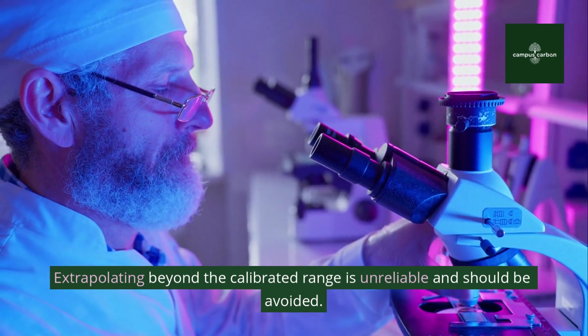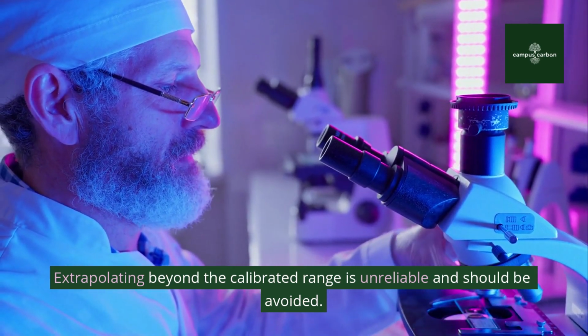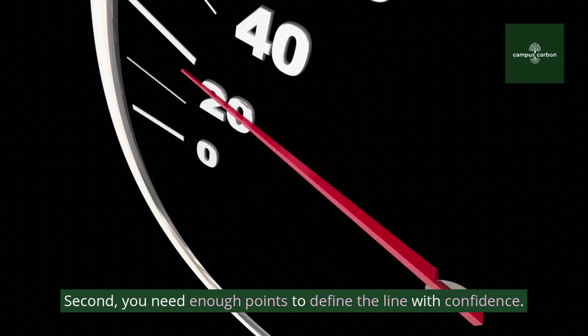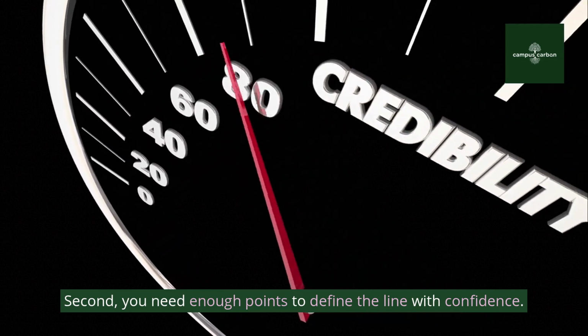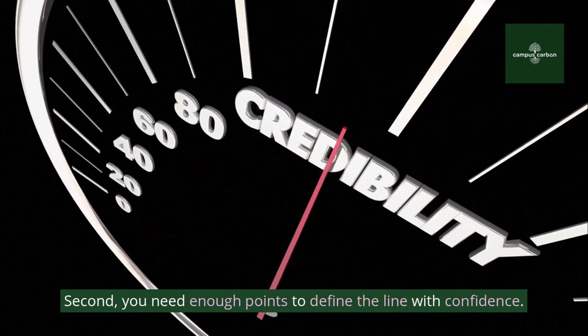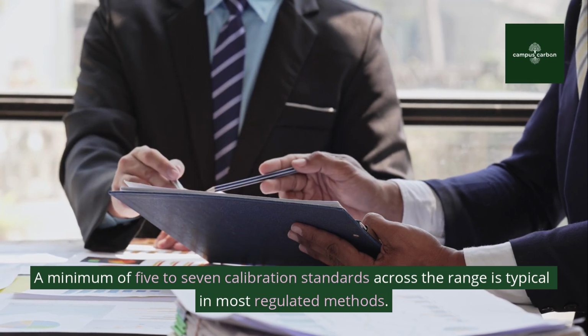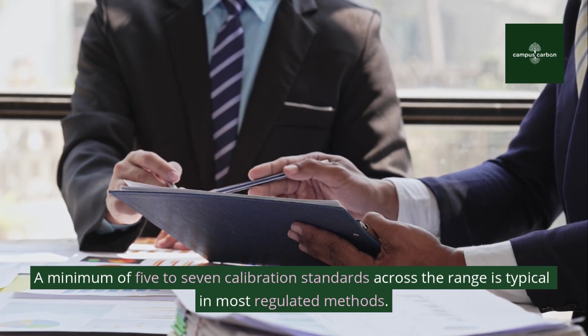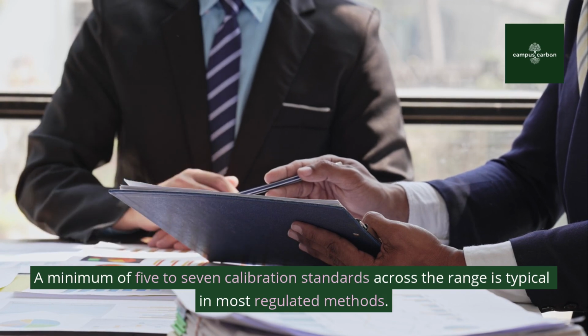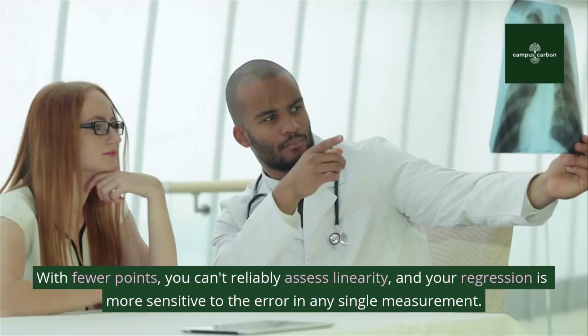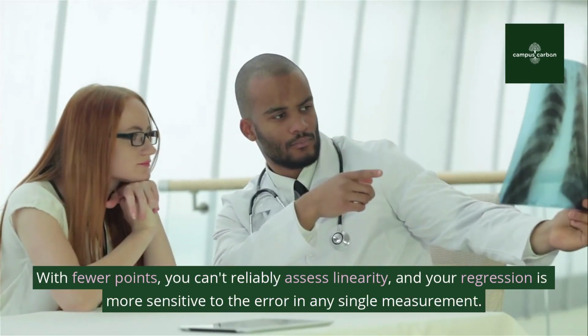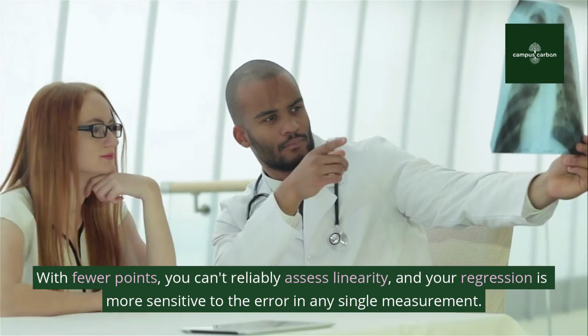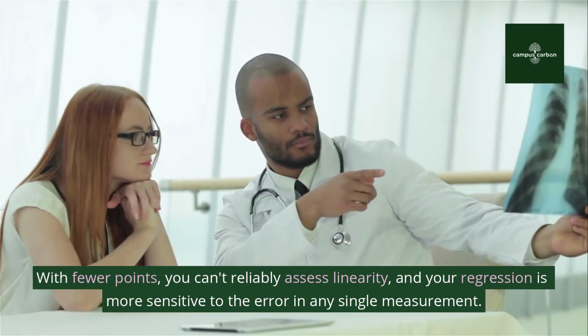Extrapolating beyond the calibrated range is unreliable and should be avoided. Second, you need enough points to define the line with confidence. A minimum of 5 to 7 calibration standards across the range is typical in most regulated methods. With fewer points, you can't reliably assess linearity, and your regression is more sensitive to the error in any single measurement.